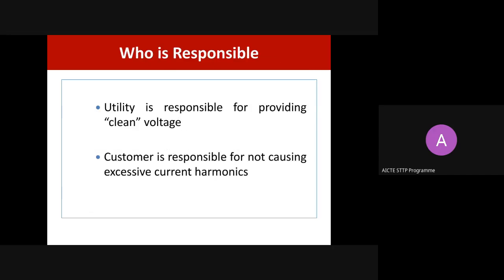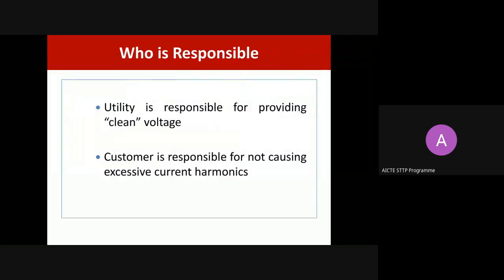Here the question is who's responsible for what? The utility is responsible for providing clean voltage at every point of service premises. At every point, the utility should ensure quality, clean voltage. Again, the customer is responsible for not disturbing the current, that is, not causing excessive current harmonics.